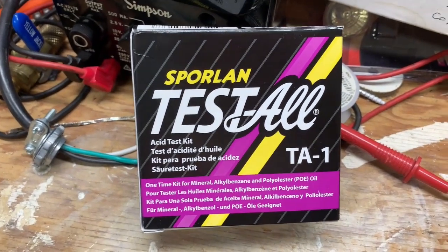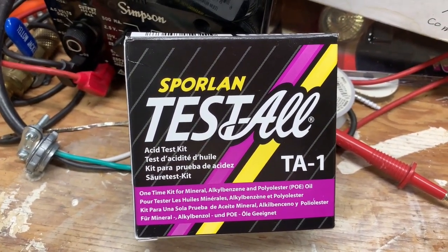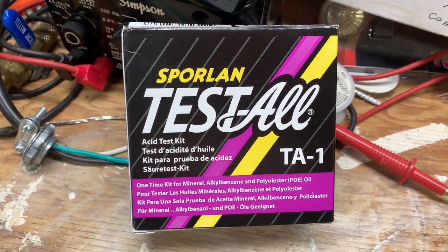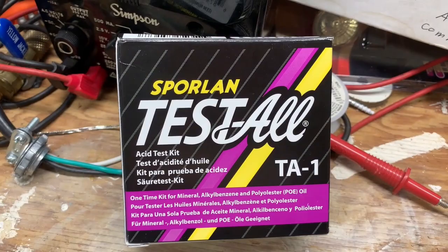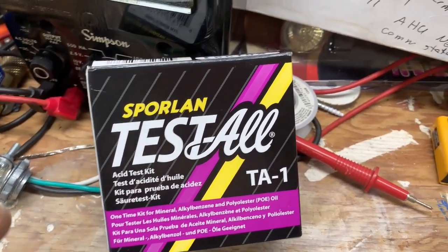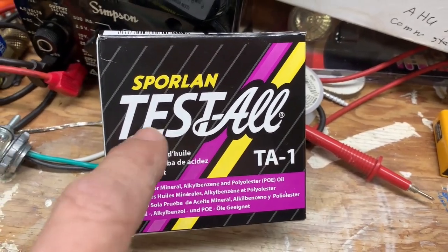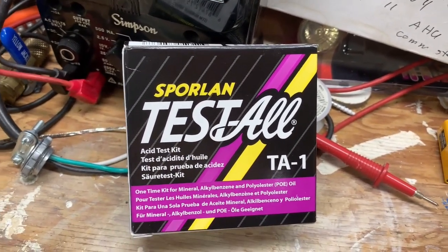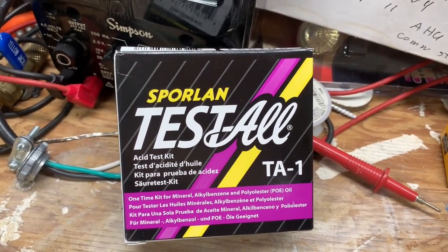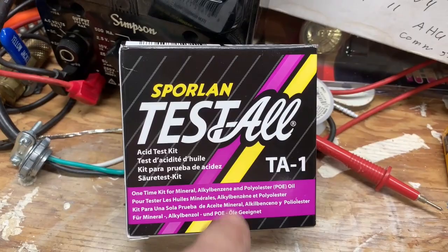I was talking on my other video about using the proper test kit to check acid in your oil. With Daikin, everything is PVE in those systems. But with Sporlan, if you notice, it doesn't say anything about PVE — but on their website, for this test kit, it tells you it will test PVE. So it's kind of poor packaging.